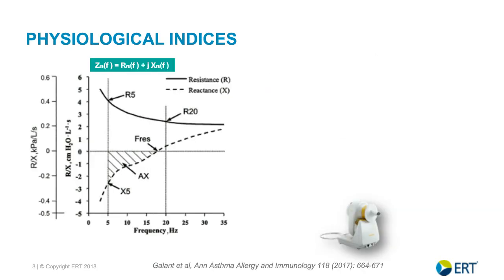So how does FOT work? If we think about the device at the bottom of this screen, where my mouse is, this is a TREMOFLO device. The device has a small piston inside it. Technology used to involve very large loudspeakers, but the advantages of piston-based technology have now been realized in this field with these very small fieldable devices that generate a pressure oscillation.